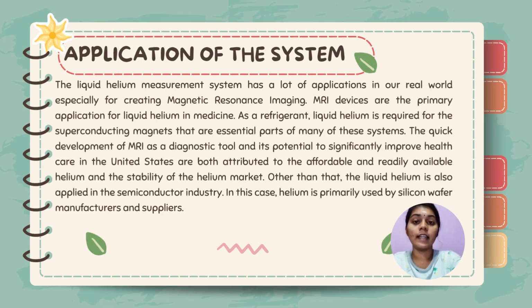Last but not least, lastly, I would present about the application of the system. The liquid helium measurement system has a lot of application in our real world, especially for magnetic resonance imaging. MRI devices are the primary application for liquid helium in medicine. As a refrigerant, liquid helium is required for the superconducting magnets that are an essential part of many of these systems.